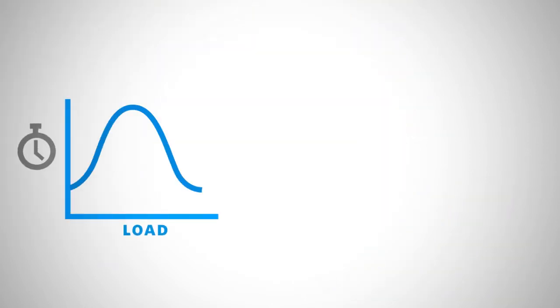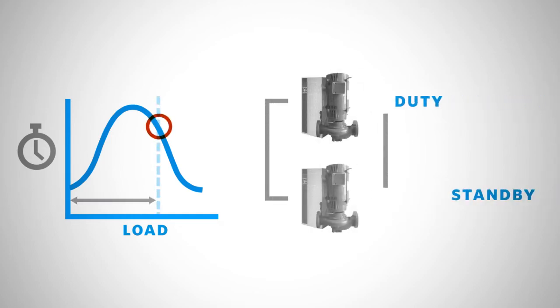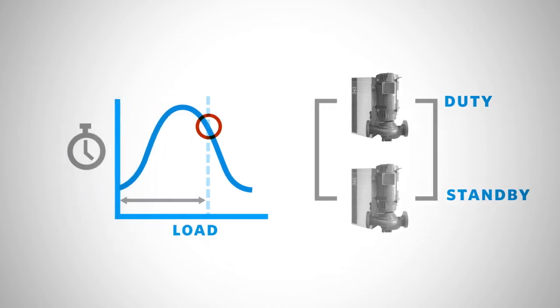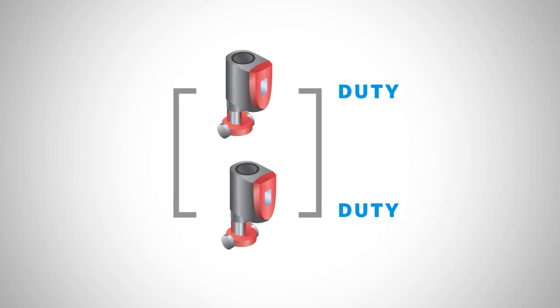Because HVAC systems function at part load for the vast majority of operating hours, it can be more cost effective to design a pump installation using multiple pumps in parallel instead of a duty standby configuration.